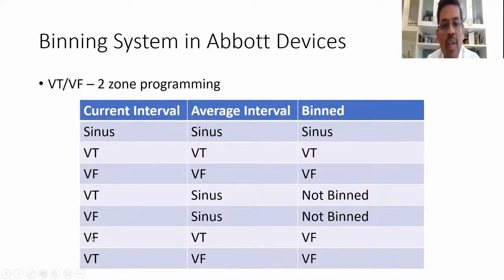On the other hand, if both current and average interval show a tachycardia or fibrillation, then it bins the interval in the faster of the two zones. So if one is VF and the other is VT, it bins into VF, and vice versa, it again bins into VF. And in contrast to the Medtronic devices, where they look at consecutive counters, the Abbott devices look at the number of counters, and if it meets the number needed to detect, which is typically 12 in a VF zone and 16 in a VT zone, and they need not be consecutive, then it diagnoses this as VF or VT accordingly.